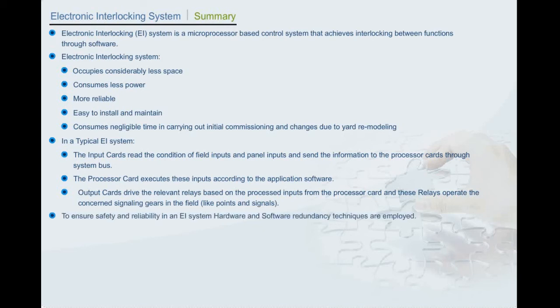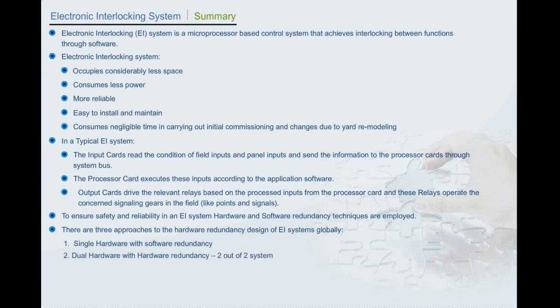To ensure safety and reliability in an electronic interlocking system, hardware and software redundancy techniques are employed. There are three approaches to the hardware redundancy design of electronic interlocking systems globally. 1. Single hardware with software redundancy. 2. Dual hardware with hardware redundancy, 2 out of 2 system. 3. Triple modular redundancy, TMR, hardware redundant, 2 out of 3 system.